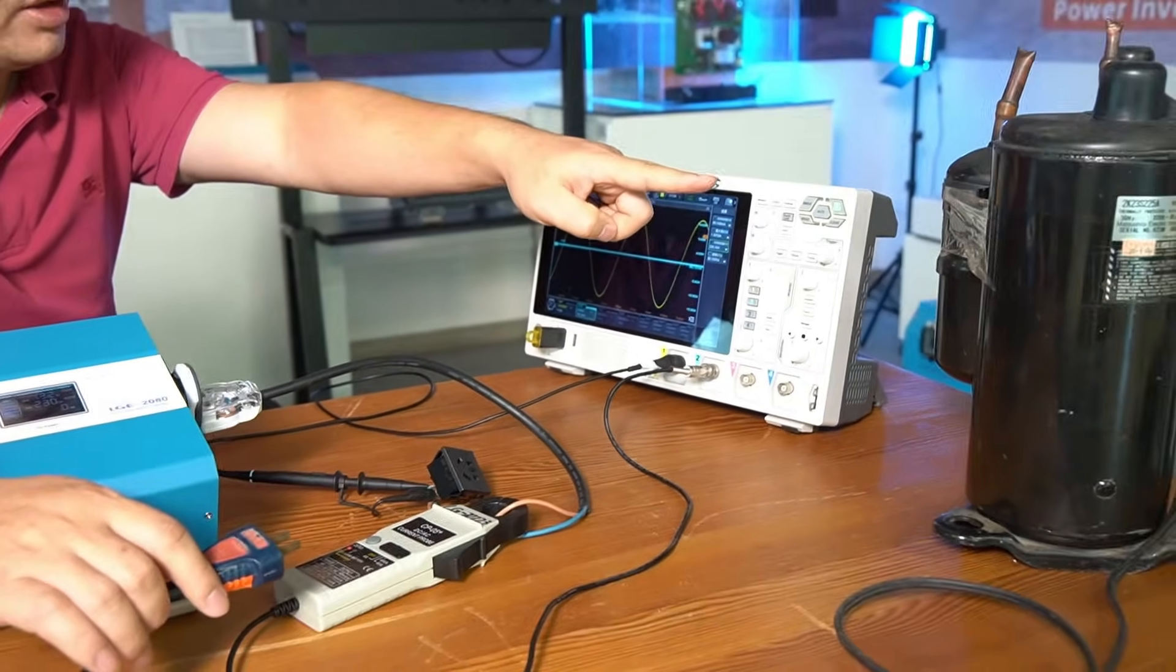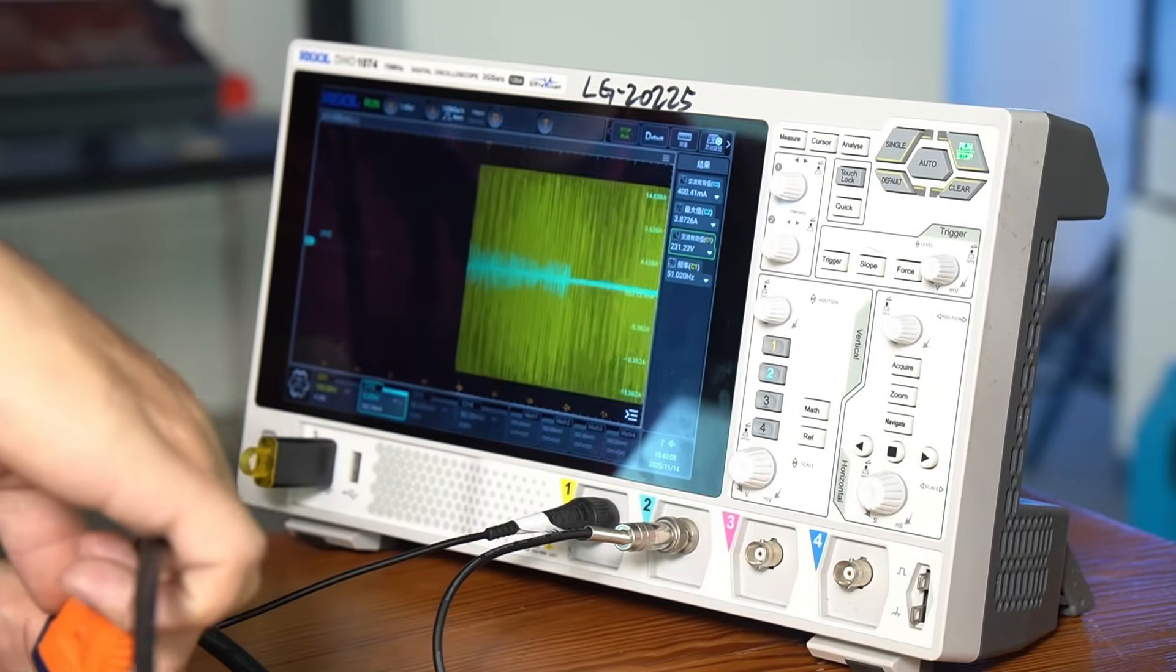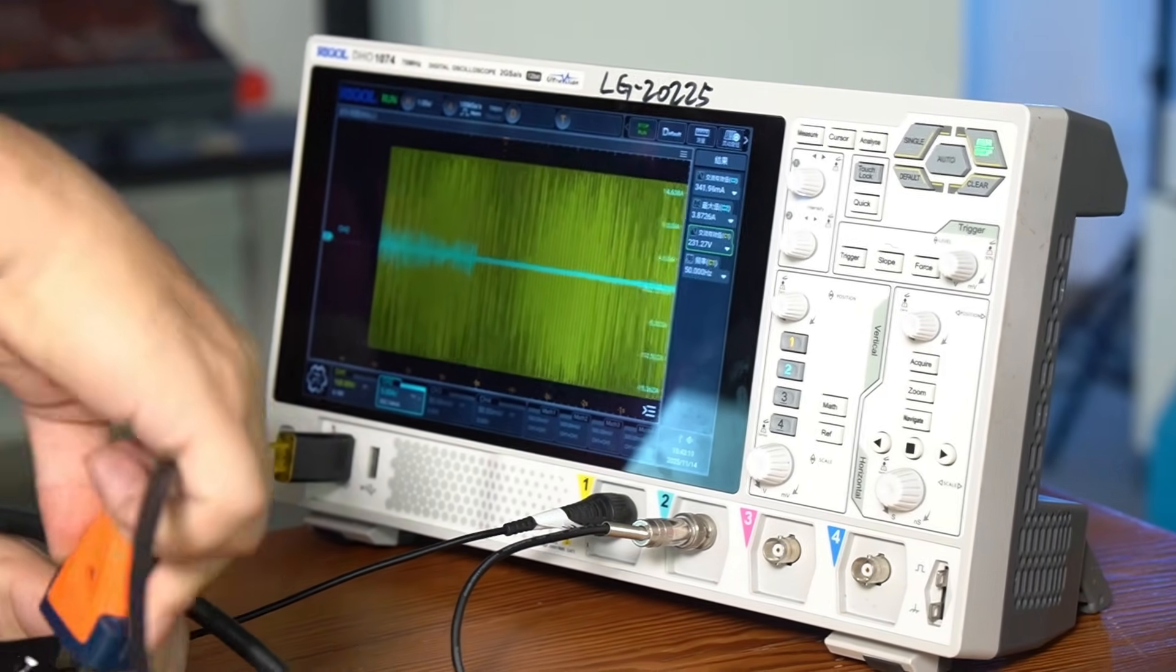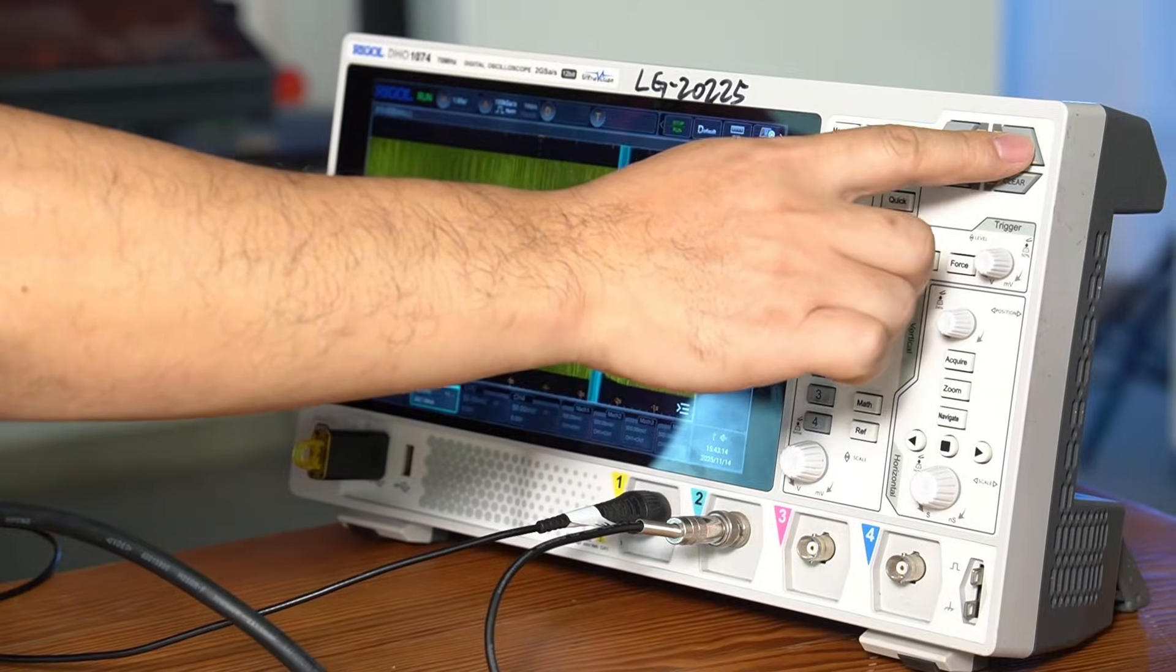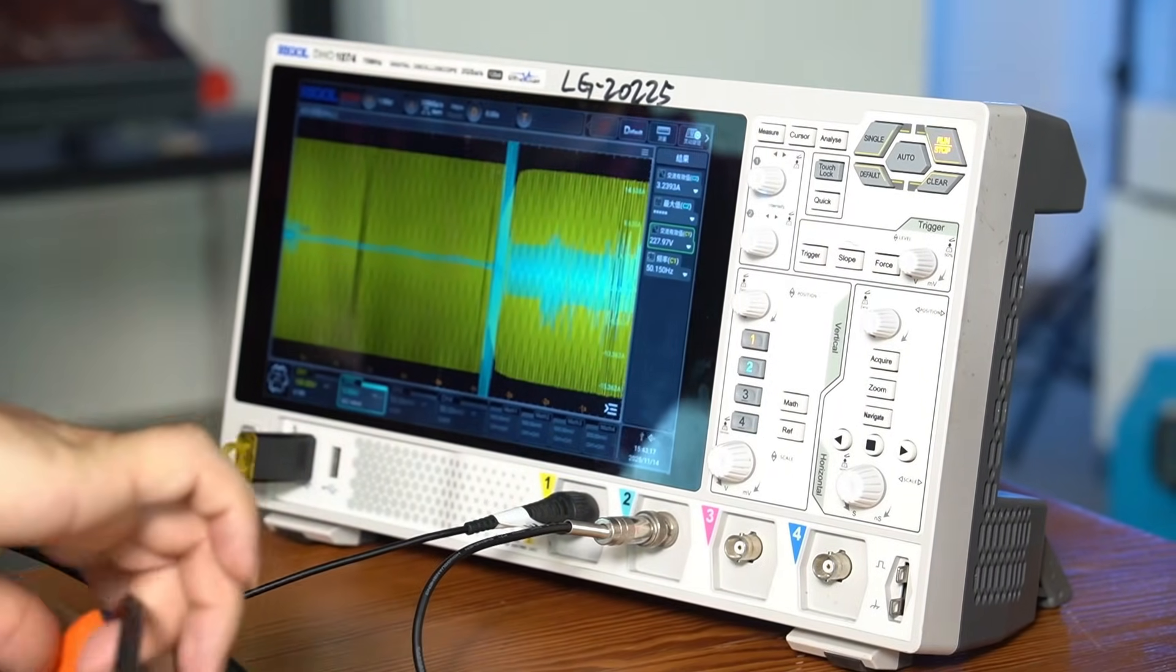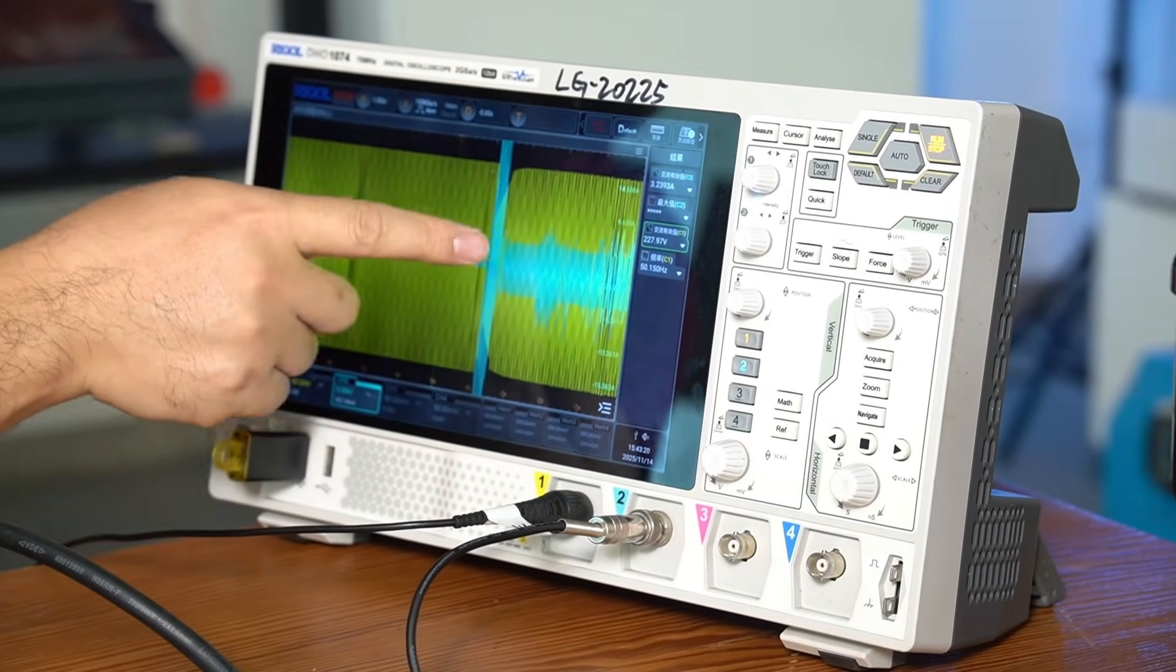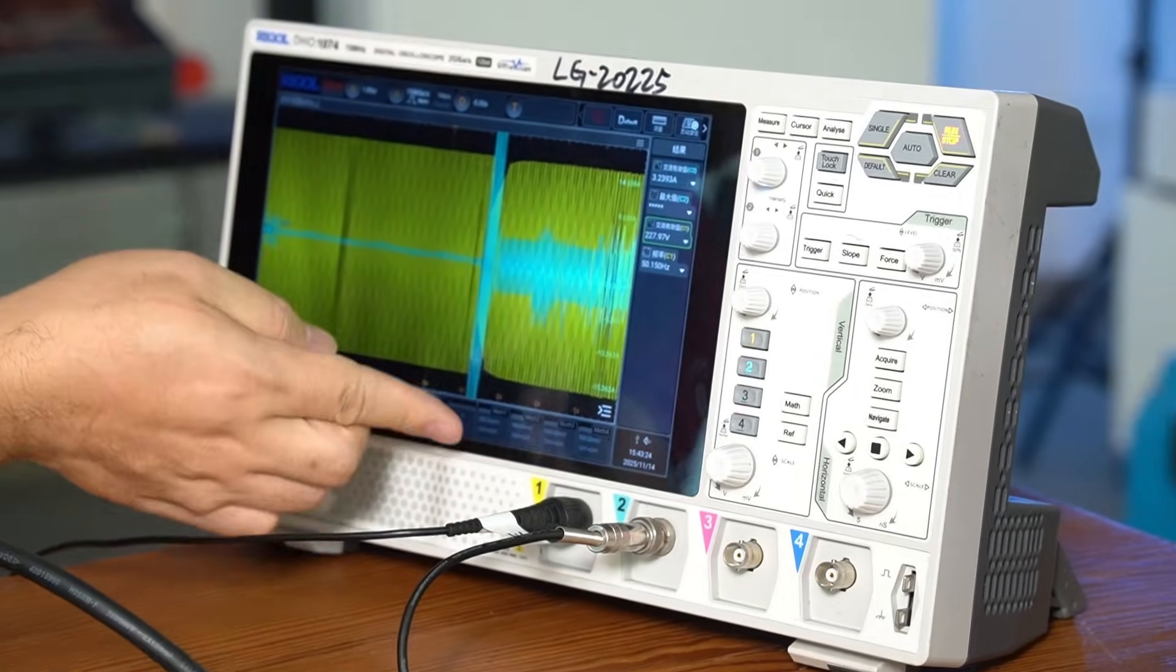Next, we'll use this inverter to start this traditional air conditioner compressor. Turning on the compressor, we can see the current waveform beginning to change. Look at this section. The waveform amplitude is very large, which is the current surge at the startup moment.